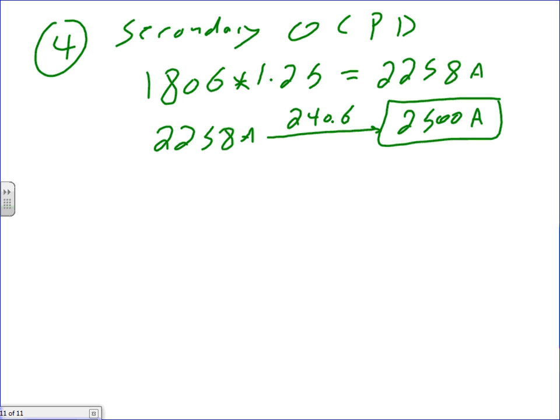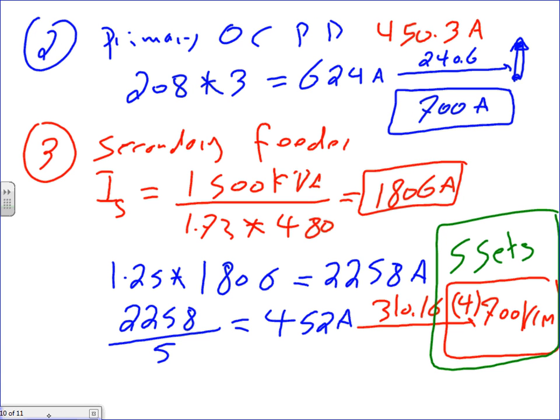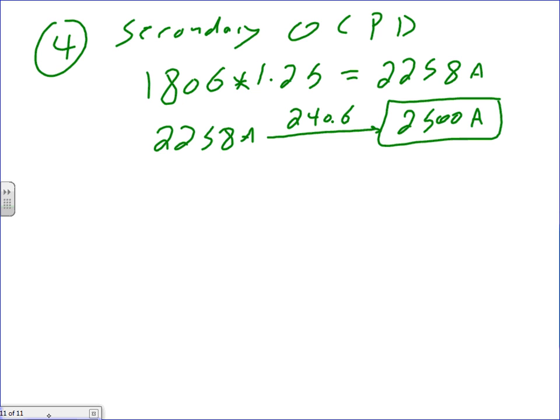2500 amp. Now, Ryan, my friend, if this is landing on the panel and your panel is 2500 amp, you have to size the conductor based on the 2500 amp. I can't emphasize that enough. Let me go back. Remember how we size these conductors? Assuming these are just feeding one machine. If you are to land these cables in 2500 switchgear, which is the most common application, then you have to size the conductor based on 2500, the overcurrent protection bus. Yes, sir. That's where it came up with the 900.